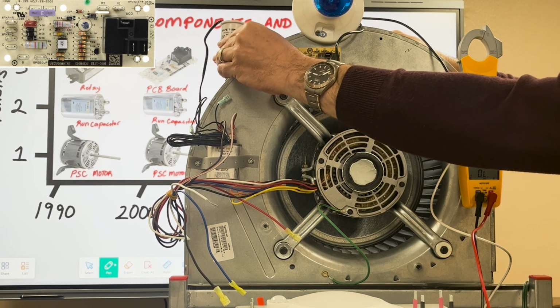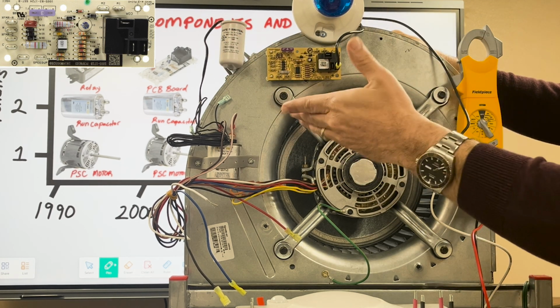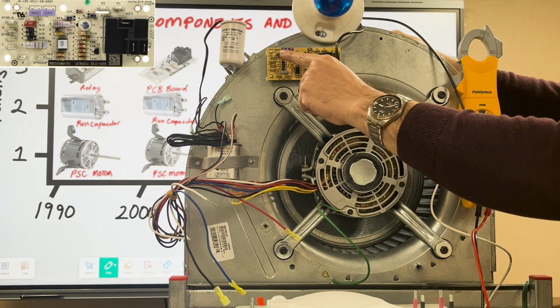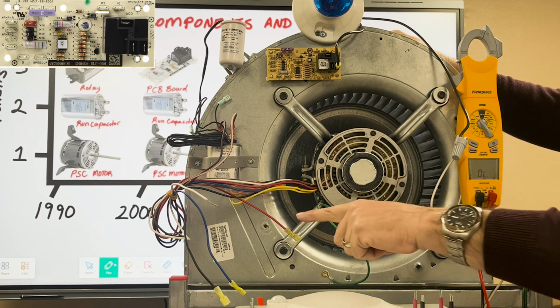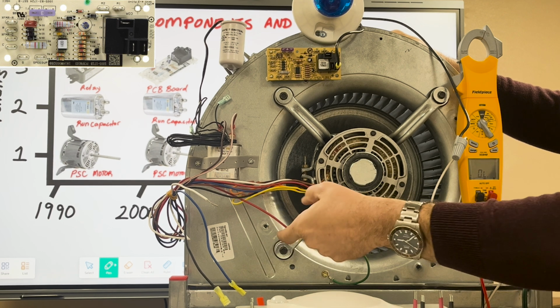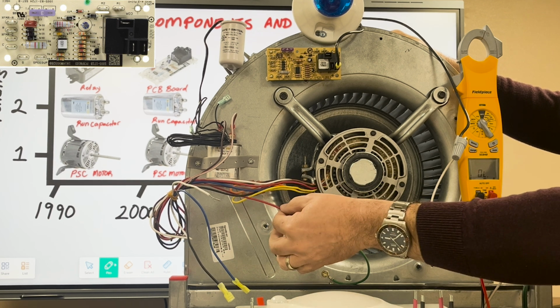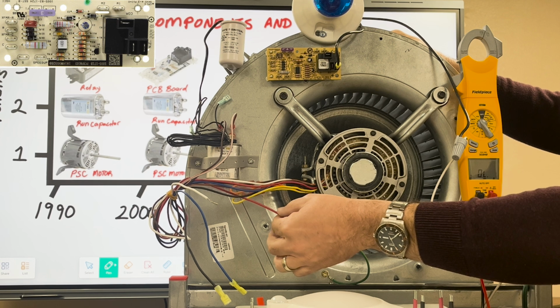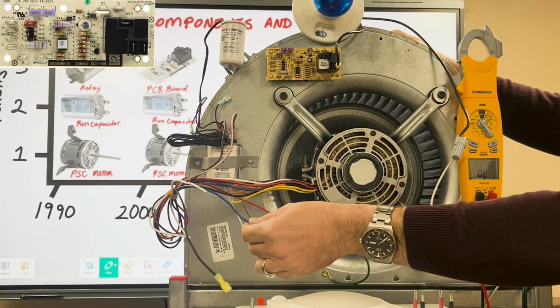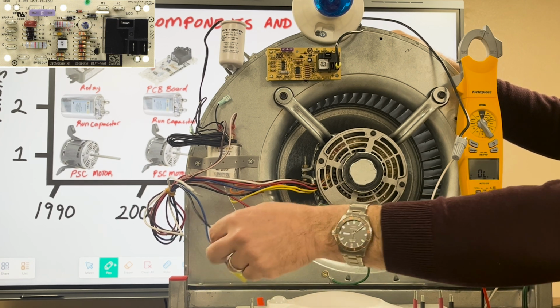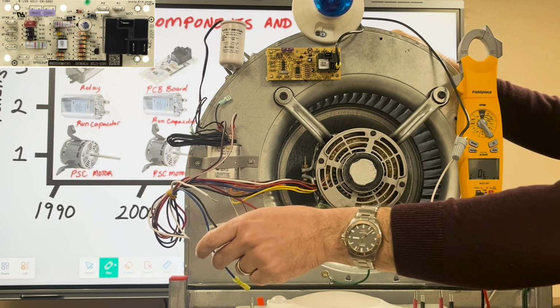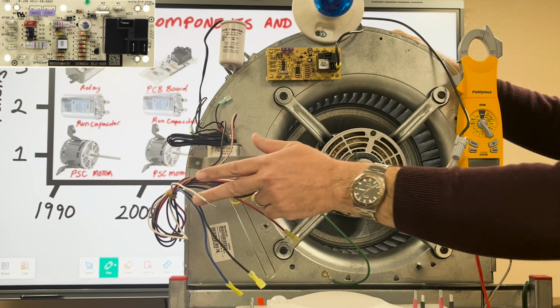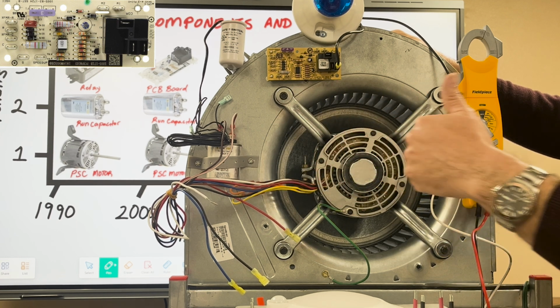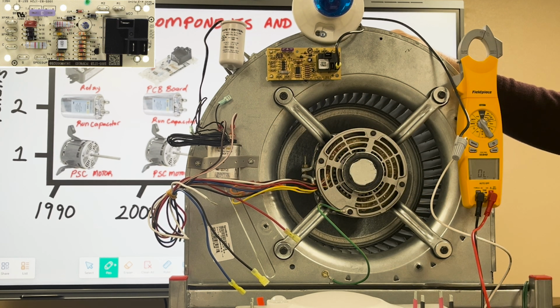Run capacitor, we've added a float switch to it so we can interrupt power. We have our 3-amp fuse on the board, and red, blue, and black wires representing our 3 speeds for common. Red for common is low speed, blue for common is medium speed, and black for common is high speed. This represents our other leg, wired to our run capacitor and start winding. And we have our power supply down here, with live 240 volts and a secondary voltage of 24 volts.